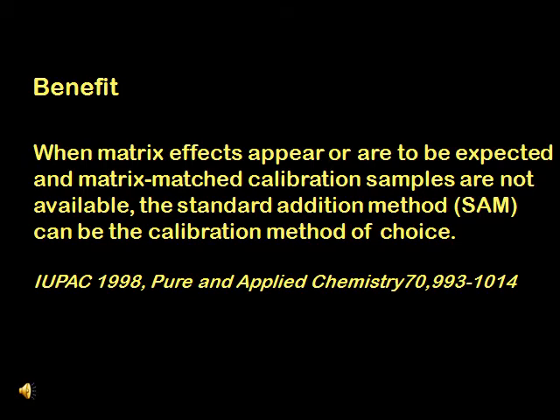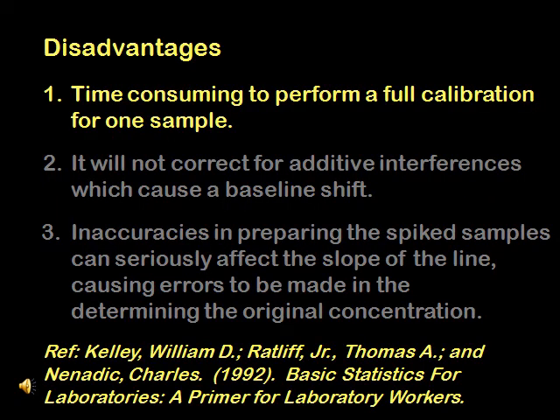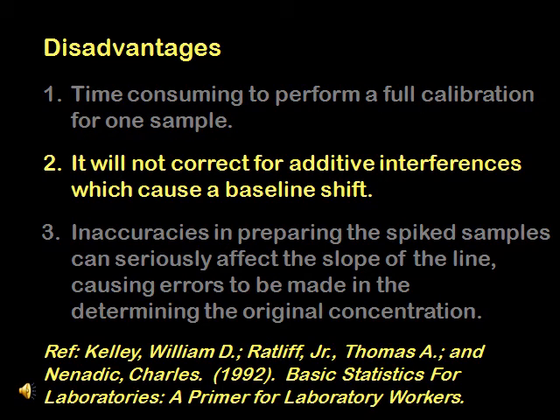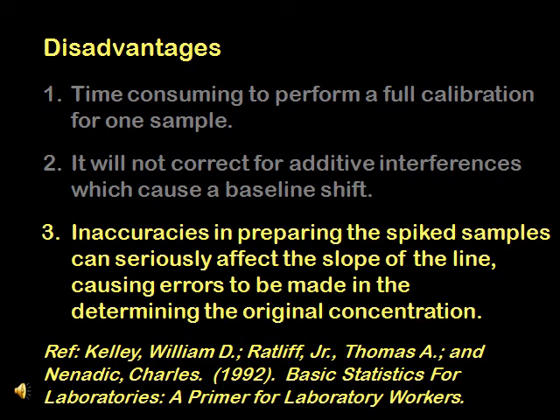A benefit of running MSA is when matrix effects appear or are to be expected and matrix matched calibration samples are not available. Then the laboratory has an option of running the standard addition method. Some of the cons in running an MSA are: first, it is time consuming to perform a full calibration for one sample; second, it will not correct for additive interferences which cause a baseline shift; and third, inaccuracies in preparing the spike sample can seriously affect the slope of the line, causing errors to be made in determining the original concentration.